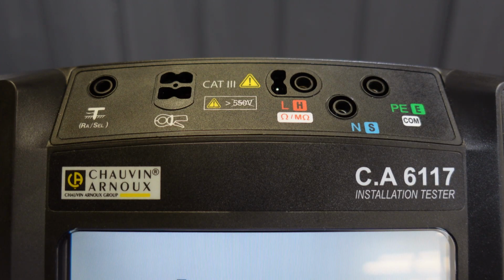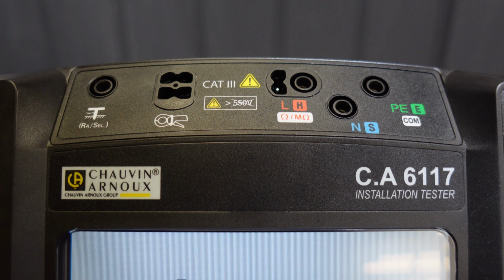Our testing interface is located at the top of the instrument, where we have, from left to right, ports for an earth probe, the C177A clamp accessory, the remote test probe, and standard 4mm jacks for line, neutral and protective earth. The line jack is also used for the resistance, continuity and insulation resistance functions, along with the PE jack, which operates as the common terminal for those tests. The H, S and E terminal designations are used with the earth spike testing detailed in another video.